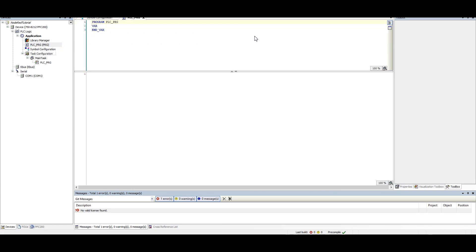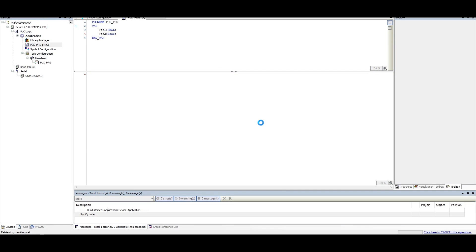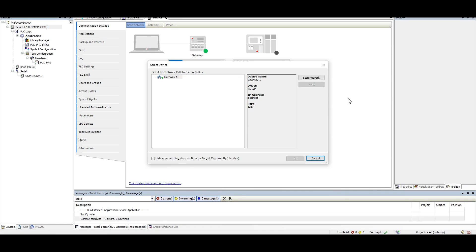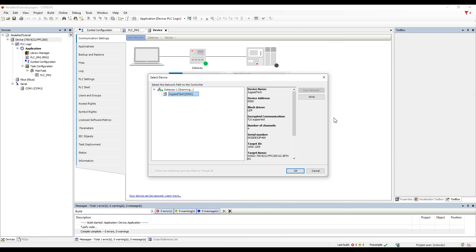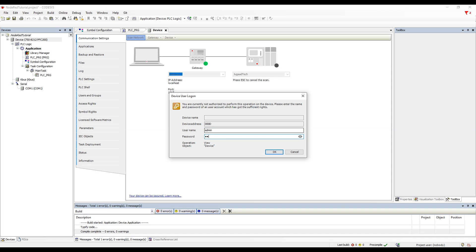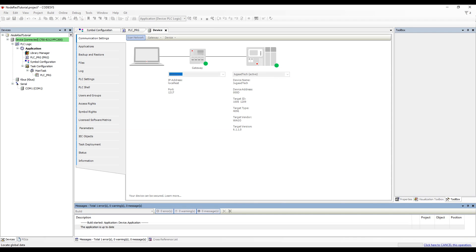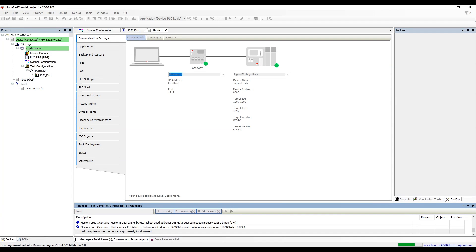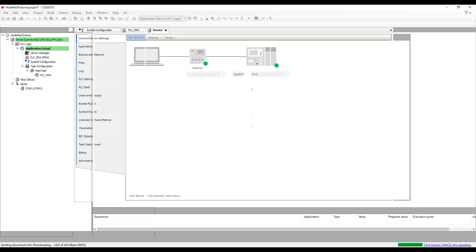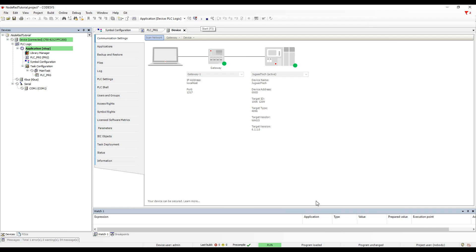Once we have configured the symbol configuration we will define the signals. I am defining one analog signal and one digital signal: VAR1 as real and VAR2 as boolean. Once these signals are defined, let's build the project. Once the code is built we can see that signals are appearing in the symbol configuration, and then we can download the code into the PLC. Once downloaded, we will go into run mode so that the OPC UA server is started and exposes all the signals defined in the symbol configuration.